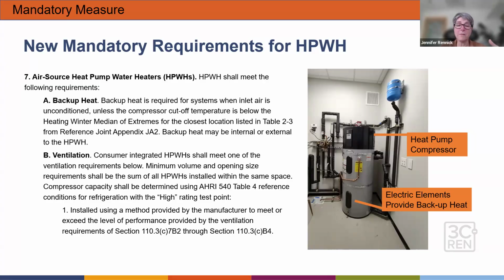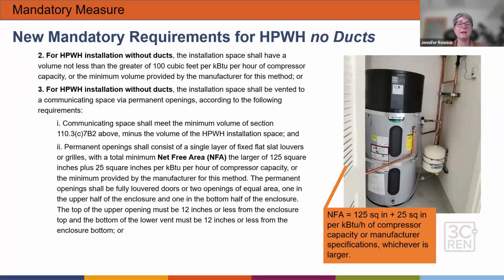And you also need a certain amount of ventilation for that heat pump to operate because that heat pump depends on the ambient air temperature to extract heat out of that air and to put it into your tank of hot water. And if you install it without ducts, then there's certain minimums you need to meet based on the size of the compressor.